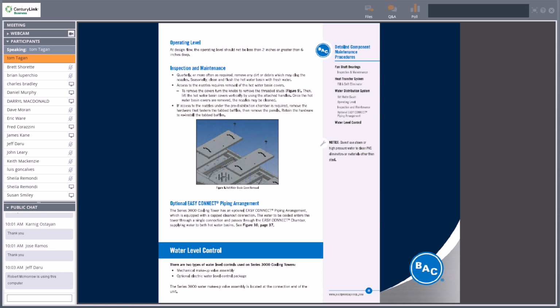These are the hot water basin covers. They would be removed when you go to inspect a hot water basin. Later on, I've got a picture of someone actually standing near it. Want to be very careful with gravity-fed hot water distribution basins. The nozzles are plastic, and there's a deflector plate that sits below the basin. So if you randomly take a screwdriver to start to unclog these nozzles, if they end up being clogged, you may break that deflector plate from the nozzle and cause just as much problems as having a plugged nozzle. So be careful. Most of them twist out by hand, and you can clean them and pop them right back in.